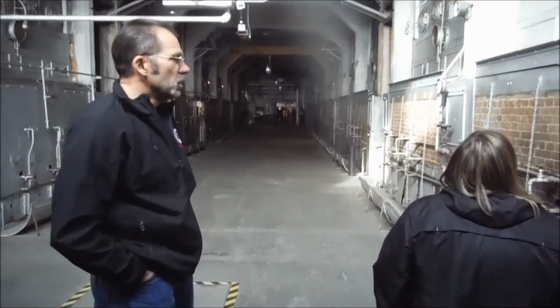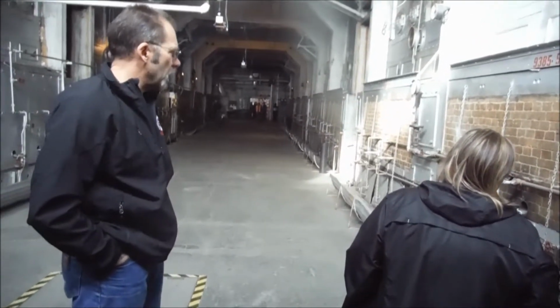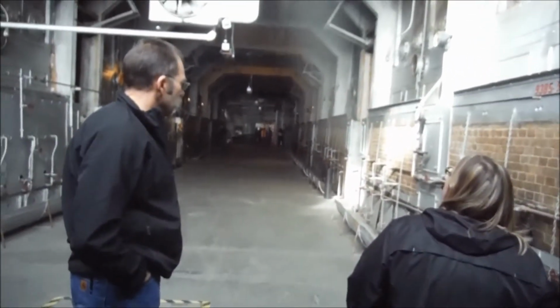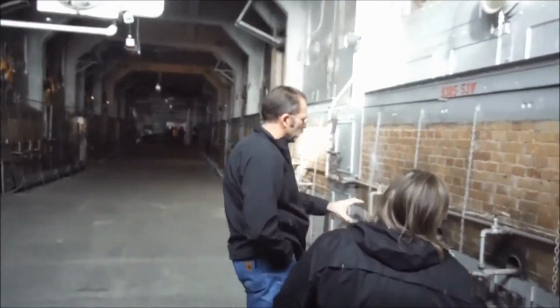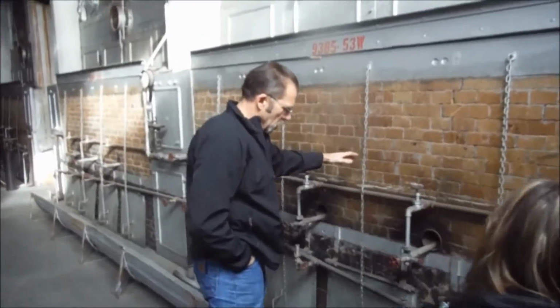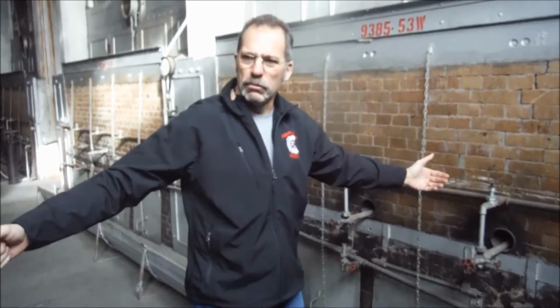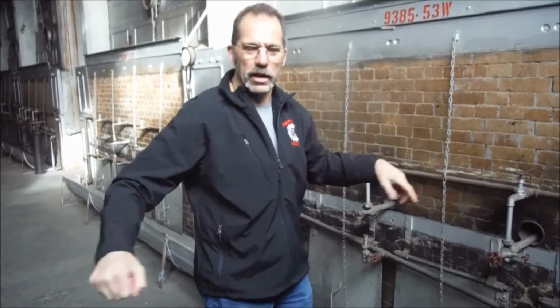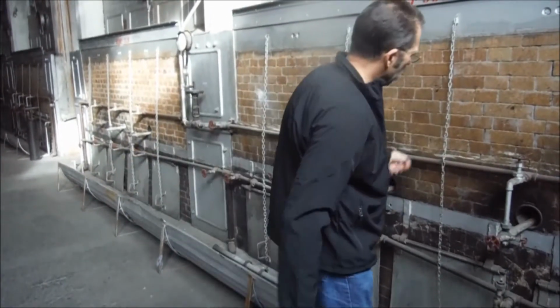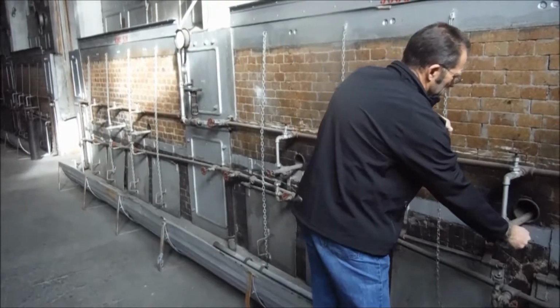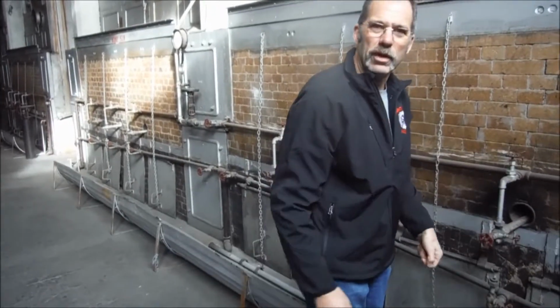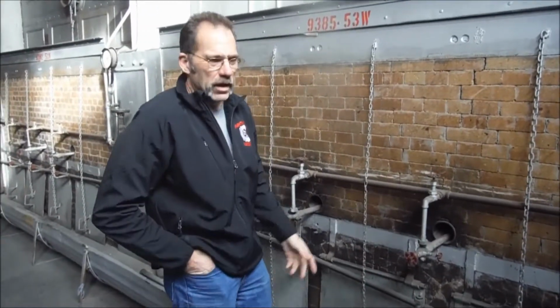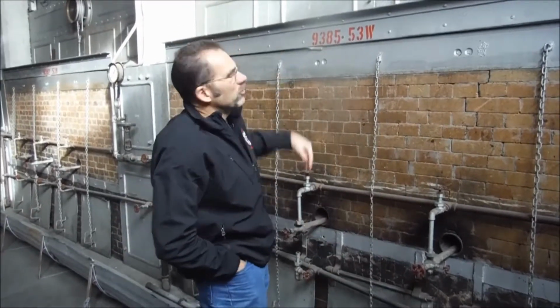Oh, okay. Well, the boilers I operated, you would have a hole that you would open and a long metal rod with a lit rag on the end of it, and you would light it and stick it in, and then you'd hold it in there, and then you'd open this valve and spray in some fuel and get it lit, and then over time you'd slowly heat up the boiler until you were making steam.